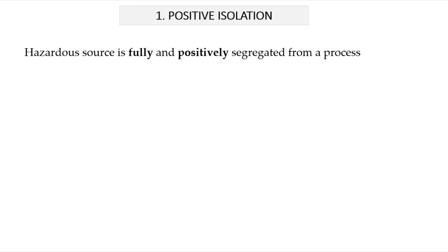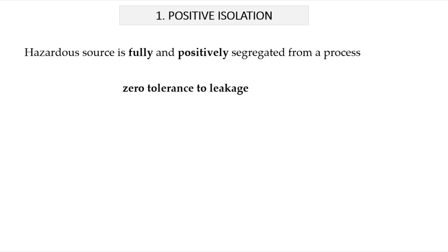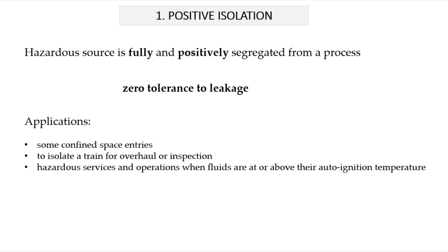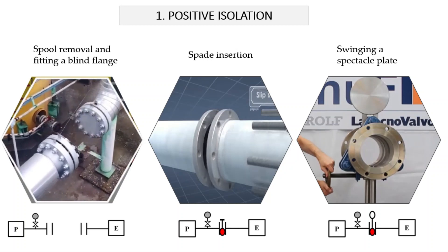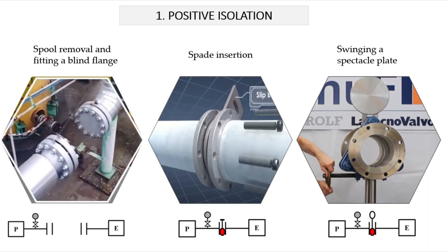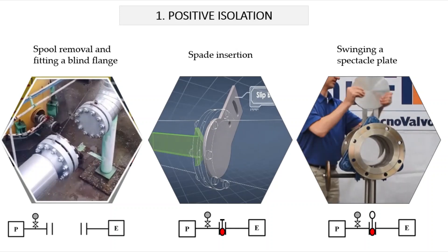With the order of criticality, it starts with positive isolation — the method where the hazardous source is fully and positively segregated from a process. This method is applied if there is zero tolerance for leakage to the system, such as some confined space entries, to isolate a train for overhaul or inspection, for hazardous services and operations when fluids are at or above their auto-ignition temperature. It can be achieved by either pipework removal and blind flange installation, or insertion of a spade or swinging of a spectacle plate.